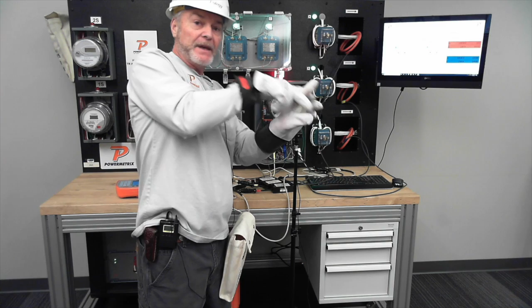You got to remember, when you start cramming anything that's picking up current around something, but I'm touching other things on there, it can tend to pick stuff up. Unfortunately, it's the nature of all our equipment out there. If there's nothing to keep it from picking that current up, it's going to pick it up and think there might be an issue, like we've got one wire run over to the wrong phase or whatever. So it says that's too much for me to accept and say that's a good test.